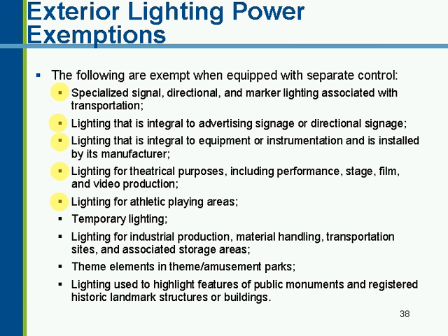Lighting that's used for the playing area itself would be exempted, but not other auxiliary areas. Temporary lighting, of course, is just temporary. It doesn't need to be counted. Lighting for industrial applications, material handling, transportation, etc., that lighting can be exempted also if it's considered that classification.